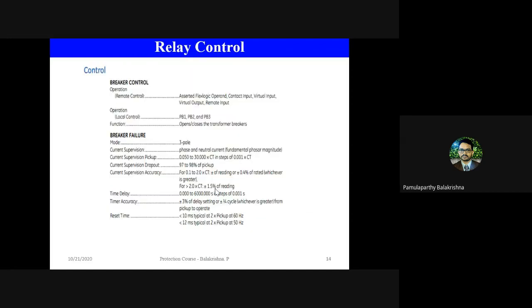Then, once you have defined the protection settings in the relay, the next major task is the control action, meaning you need to control the breaker. As I told, the digital output present in the relay is connected to some form of output within the relay, and that comes as a remote input to the breaker. So near the breaker also there will be a small electronic device which receives the signals from the relay. Okay, so a remote input means that the remote input for the breaker is coming from a relay. Within the breaker, you can configure this as enabled for remote control or local control. If you forgot to configure this as remote control and you kept it as local control, then even though the relay sends a signal, the breaker will not trip, because you did not give the permission of remote control. So each breaker has to be given remote control.